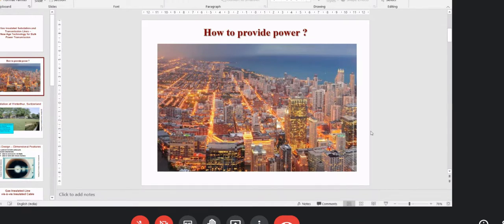That solution came as the gas insulated substation, where everything has been minimized, but air insulation doesn't work. So it is gas insulated, but that gas is sulfur hexafluoride, SF6. And SF6 also not at atmospheric pressure, because we need very high dielectric strength, so it works at the order of 6 to 7 atmospheric pressure. And then the whole thing can be minimized.